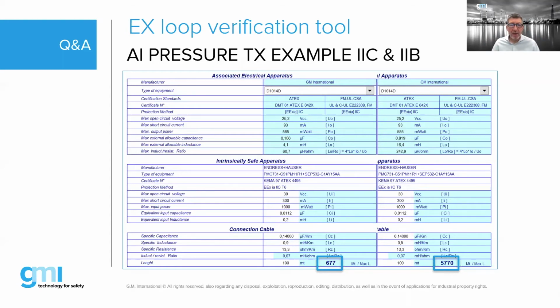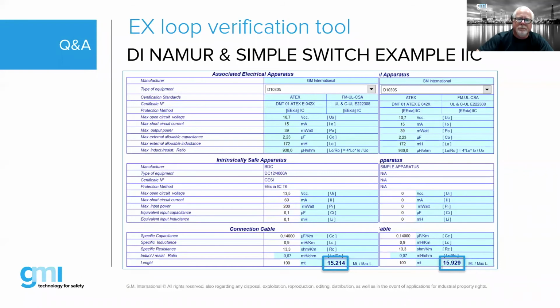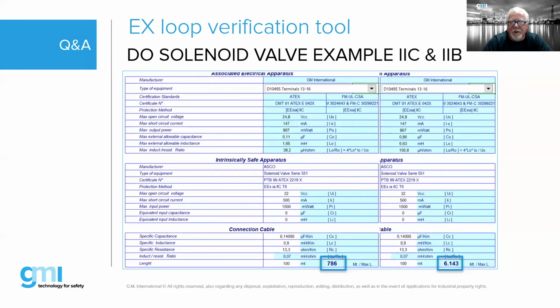The same here: I made a different example on a DI switch, comparing a simple device, so a switch, which you can see on the right side, which has no safety parameters and the only thing you look for is the cabling, and an NAMUR switch, which does have safety parameters. And you see the difference is basically nil, not applicable, because the safety parameters of a DI switch are very, very small. There's no capacitance and no inductance in the switch. It's just a switch, no stored energy.